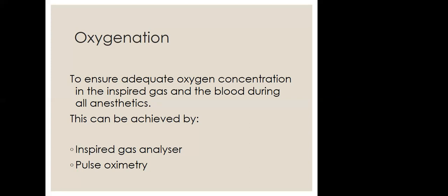During every administration of general anesthesia using an anesthesia machine, the concentration of oxygen in the patient breathing system shall be measured by the oxygen analyzer with low oxygen concentration limit alarms. Pulse oximetry gives us information about heart rate, saturation, and perfusion index. I will discuss it later.